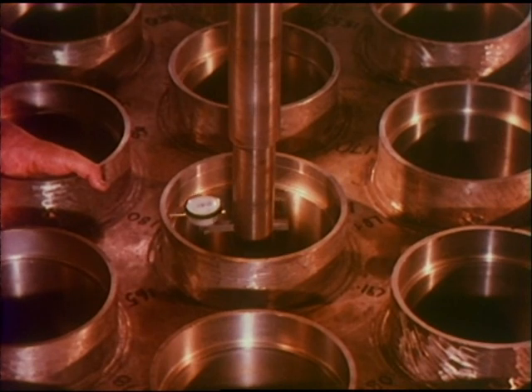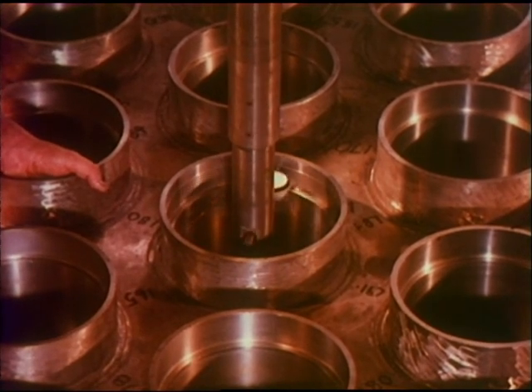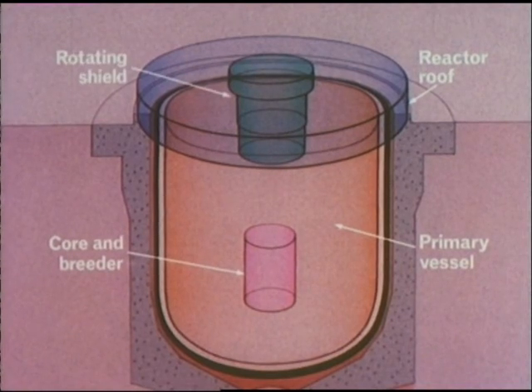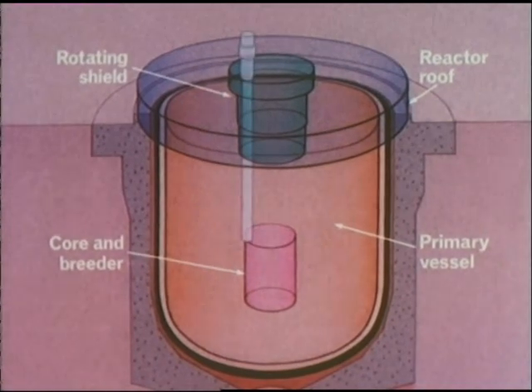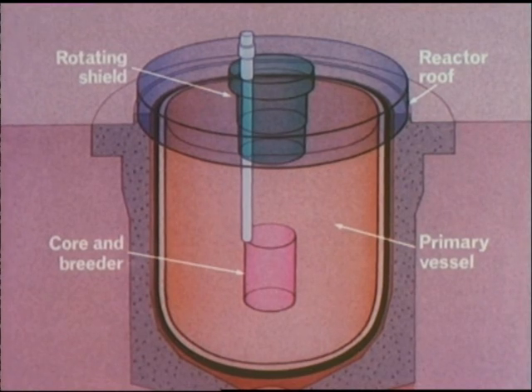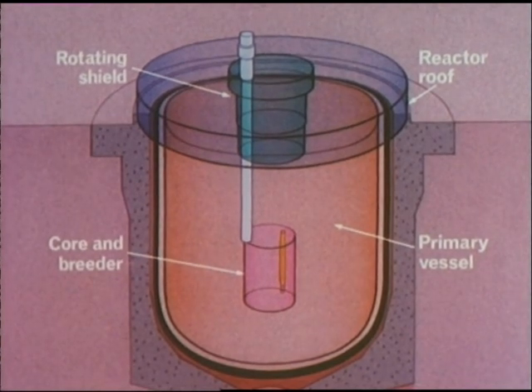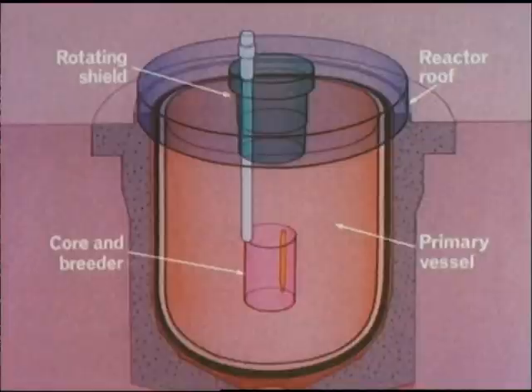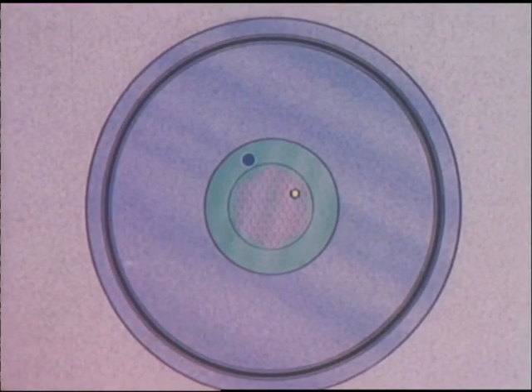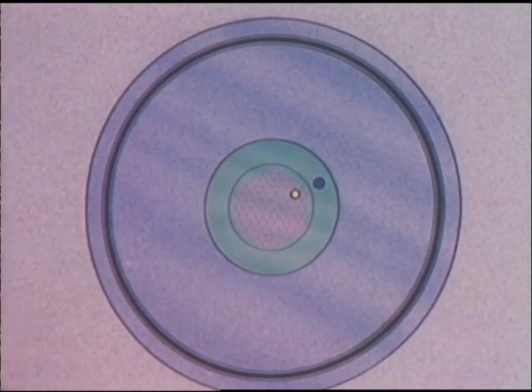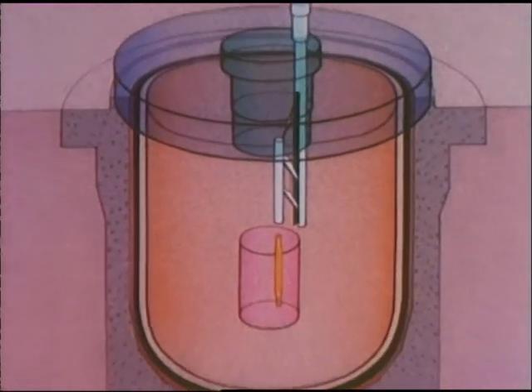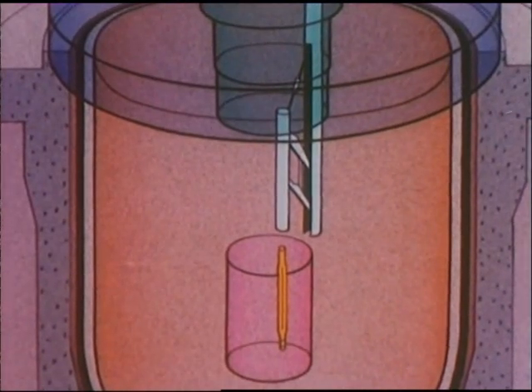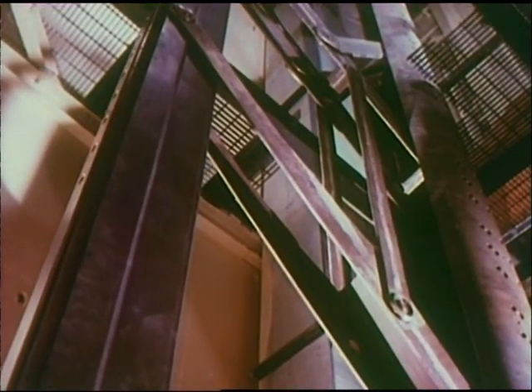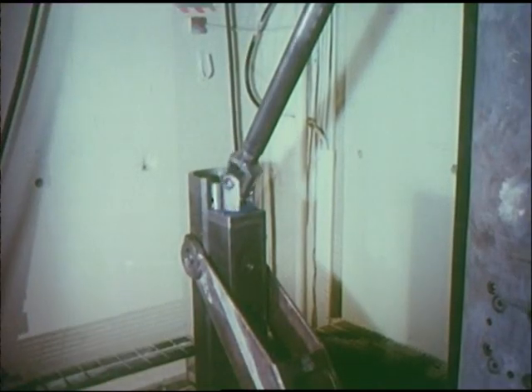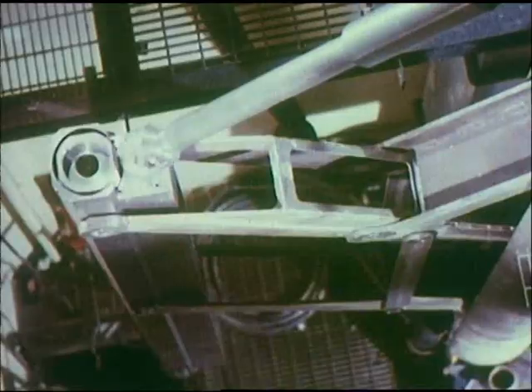Offload refueling, involving the use of this rotating shield, was effected in the following way. This simplified diagram shows how the rotating shield, shown blue, carries the refueling machine, a vertical cylinder containing the charge chute. When a sub-assembly, shown yellow and not to scale, is to be withdrawn from the core, the shield must be rotated until the refueling machine is radially in line with the fuel. The charge chute is then extended over the sub-assembly. In this works test, the charge chute has already been extended, and power is being applied to drive the fuel gripper down through the charge chute.